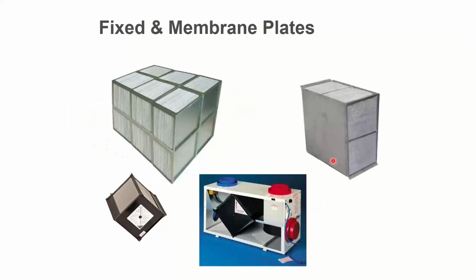Fixed plates come in both sensible or latent versions. Sensible versions would not comply with code. Latent versions would. The easiest way to tell them apart is a sensible version is going to be metal only, like the bottom left one over here. A latent version is going to have some kind of membrane in it or what looks like paper or fibrous material. I would say paper, and the ERV guys yell at me. Fibrous material that can wick moisture through without the actual air molecules.